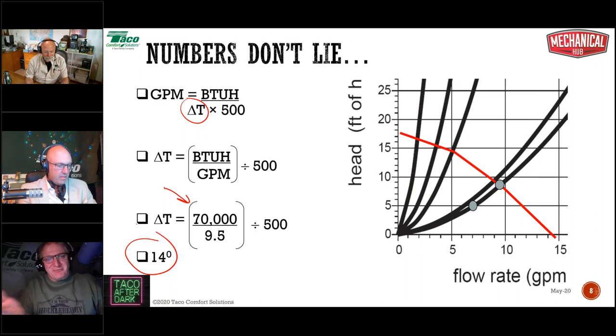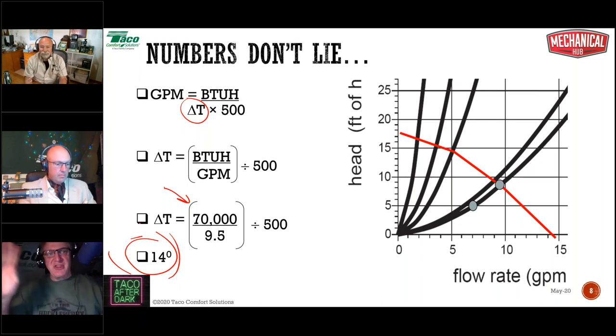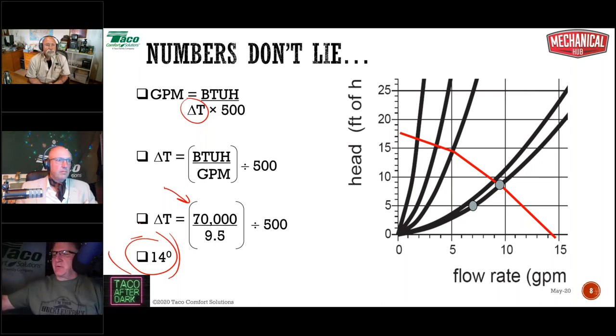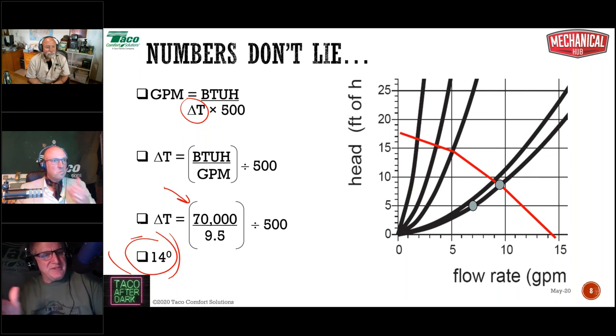All right. So this is optimistic at best anyway, people. And it's only going to happen under design conditions. The day, the outdoor design temperature we used to calculate that heat loss. That's the theoretical best it could ever be. So instead of the water going out at 180 and coming back at 160, it's going to go out at 180 and come back at 164 or 166 rather, instead of 160. So there's a difference there. All right. Think about that. Just keep that one in mind.